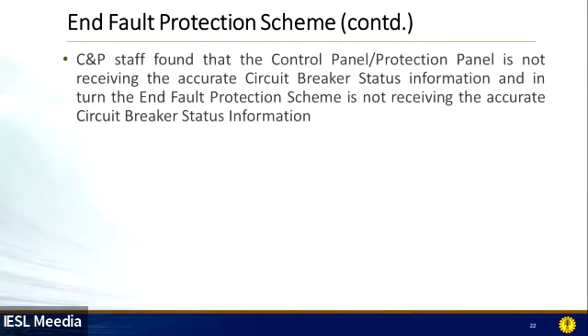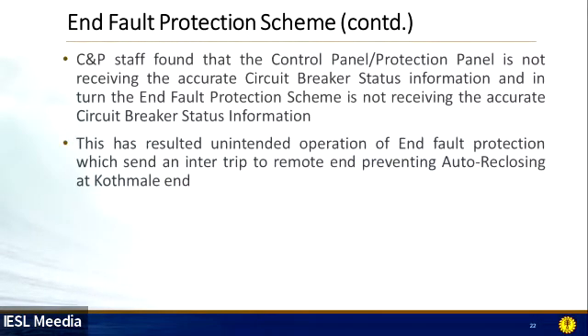Control and protection staff found that the protection panel is not receiving accurate circuit breaker status information, and in turn the end fault protection scheme is not receiving accurate circuit breaker status information. This resulted in the unintended operation of end fault protection, which sent an intertrip signal to the remote end, preventing auto reclosing at the Kotmale end.